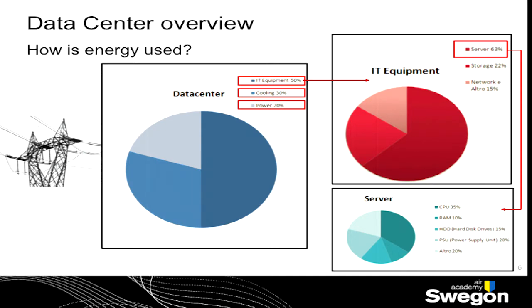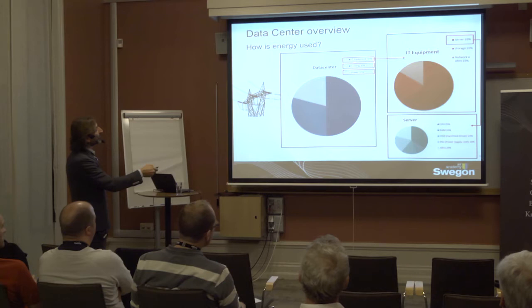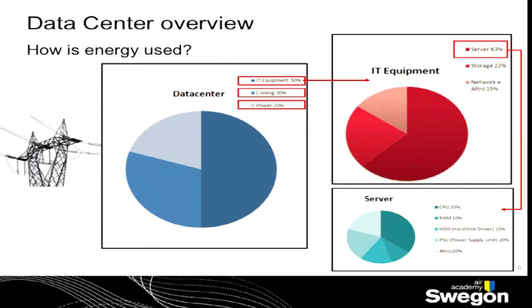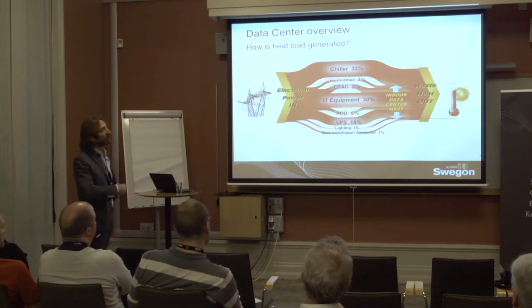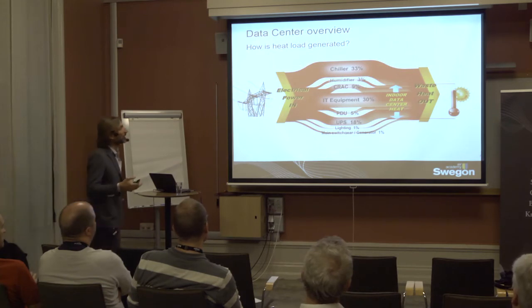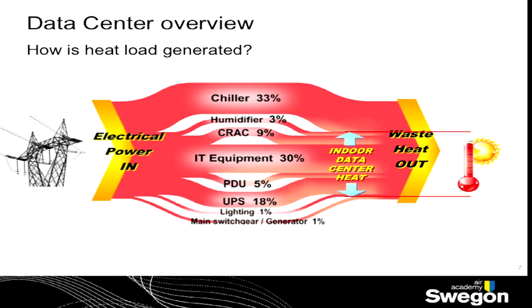How is it used in the server? You have a picture just for knowledge. The server uses more or less 60% of the IT energy introduced into a data center. But we can say roughly that cooling consumes no less than 30% of the total energy introduced. And if you consider that the energy introduced into a data center is almost completely converted into heat, it means that all this energy contributes to the increase of the temperature in the data center. Because only the chillers are completely outside of it, but all the rest, humidification if needed, the CRACs, the IT equipment, the UPS and lighting is always inside the building. It means that all this energy is converted into heat inside the building. And of course, it has to be removed.